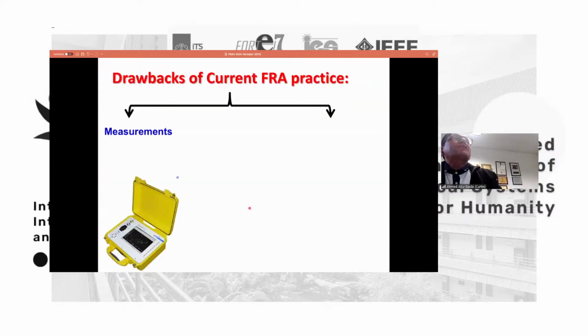So what are the challenges in this technique? As I told you, the measurement is very simple, very easy, and anyone can perform it. But the technique is so far offline. So we have to take the transformer out of service, which will cause interruption to your grid. That's from the measurement point of view. Also, this device here is not very reliable for minor deformation. So when you have emerging faults that start at a very minor level, that device cannot detect them.